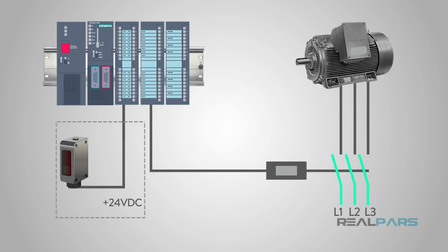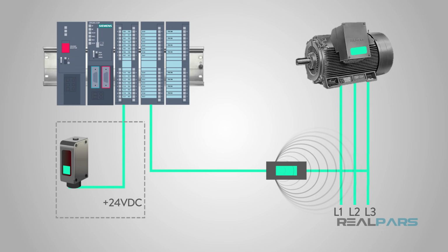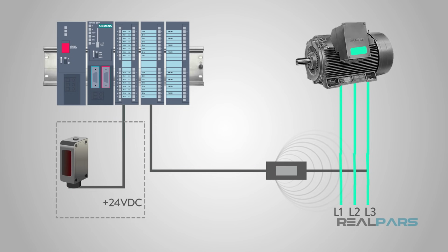Whenever a box is placed on the conveyor belt, the photoelectric sensor is blocked. The sensor acts as a switch that will send the low voltage to the coil of the motor starter. Once the coil is energized, the electromagnetism closes the contacts of the motor starter, allowing the high voltage to pass to the motor and run the conveyor belt. Once the box is past the photoelectric sensor, it will turn off the motor starter by removing the low control voltage.